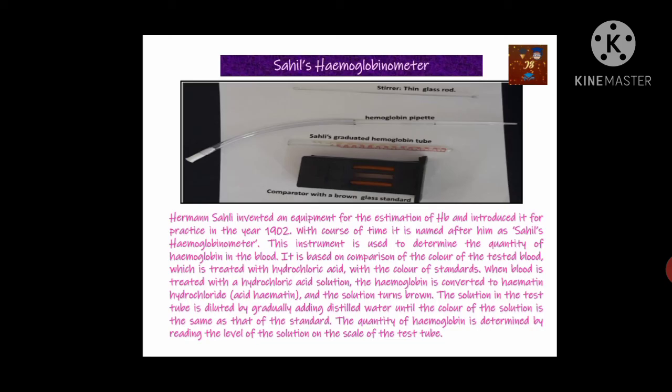The next instrument is Sahli's hemoglobinometer. As the name implies, it is used for the estimation of hemoglobin. Hermann Sahli invented this equipment in 1902, indicating the long-recognized importance of measuring hemoglobin. The main parts are a glass rod used to mix the blood sample with hydrochloric acid, a hemoglobin pipette to measure the blood sample, and a comparator tube in which the HCl is mixed with the blood sample.